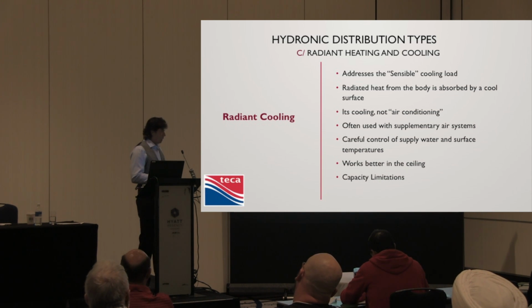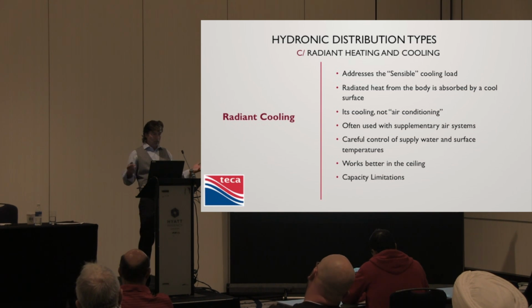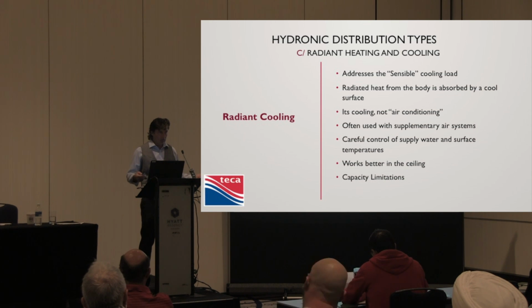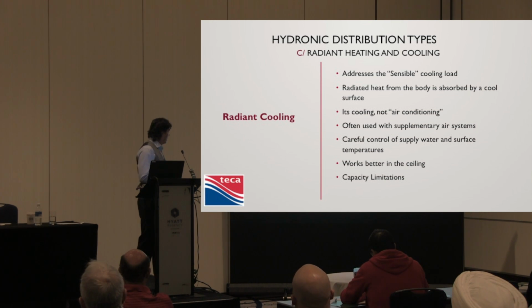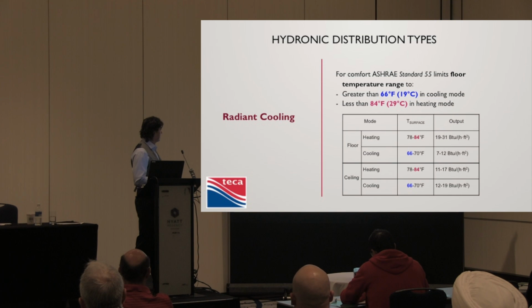So it actually works better in the ceiling in this case. That's why the Germans like to put it in the Becker mats. And it's also got capacity limitations. The same limitations we have with absorbing or rejecting heat from a slab, we have the inverse of that with radiant cooling. And we could talk about those actually.